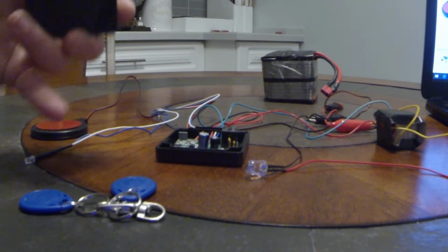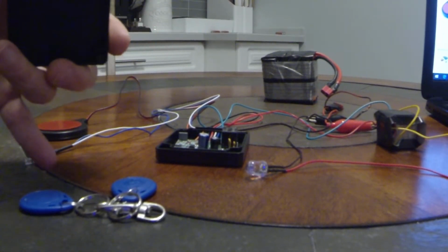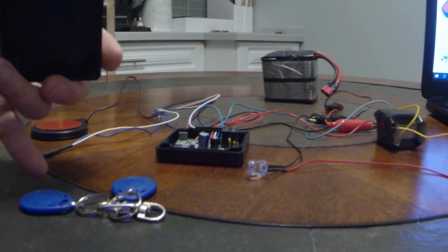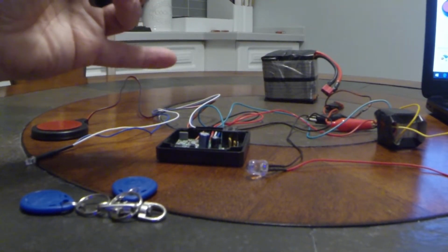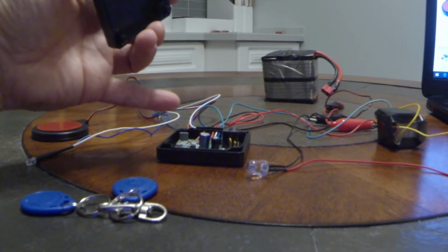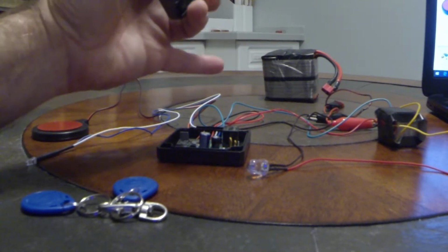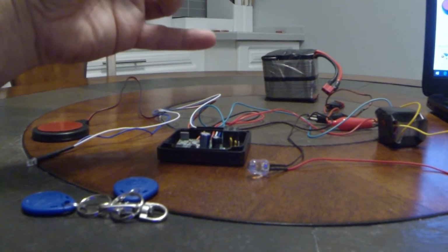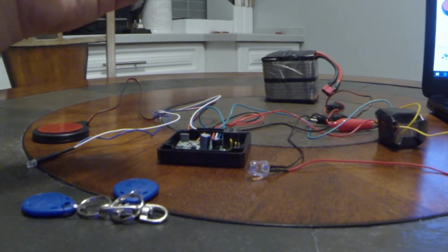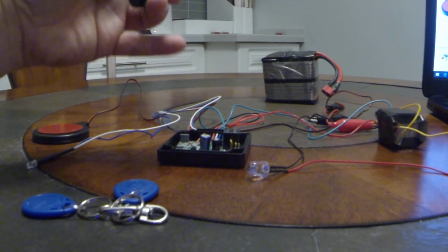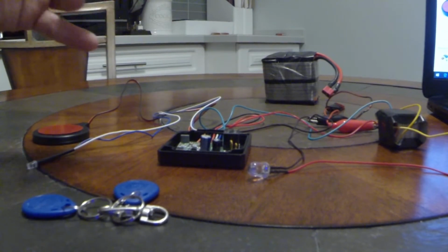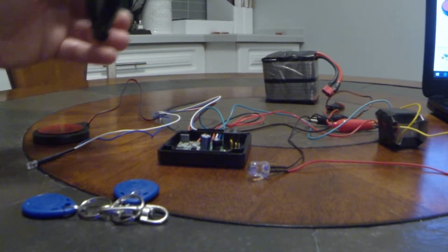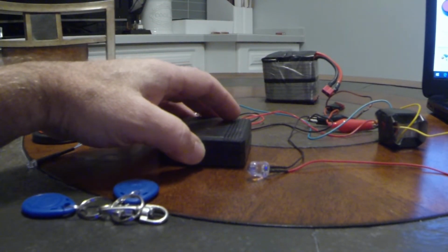The system recognizes two different key tags. There are serial numbers on them, and I guess these have been hard-coded into the firmware of the control box. What it does is, the green wire, which is typically connected to ground by default, gets turned off when the RFID tag is recognized. So like I said, it turns the circuit off, not on.